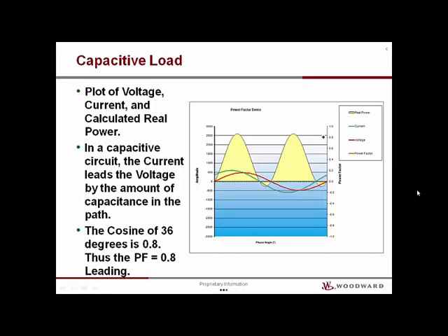This plot of voltage, current, and calculated real power is an AC generator with a purely capacitive load. Due to the capacitive reactance nature of capacitors, the voltage is delayed behind the current. In this case, the shift is 36 electrical degrees. The cosine of 36 degrees equals a 0.8 leading power factor. It is not very common to have a leading power factor.